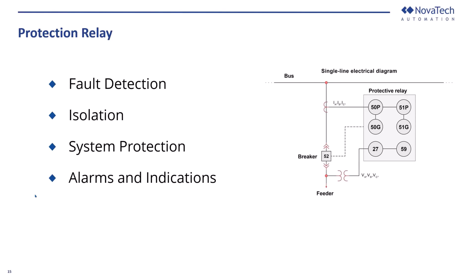Coming to the types of protective relays, on the right-hand side we've shown a few of the devices that we're trying to protect, whether it's a transformer, a bus, a generator, a line, or feeder protection. There are various relays for different functionality, and they vary in characteristics, whether they use differential, distance, overcurrent, directional, under or over voltage, under or over frequency, or ground fault. Let's take a look at the differential relay. It typically protects transformers and generators from localized faults. It compares the current entering and leaving a zone to detect faults within that zone.